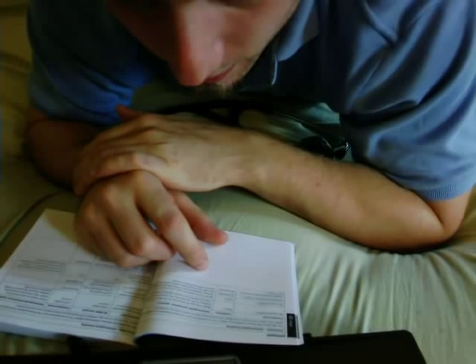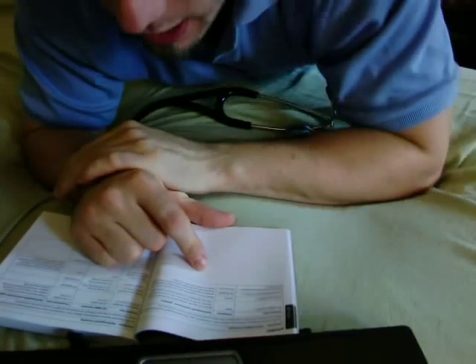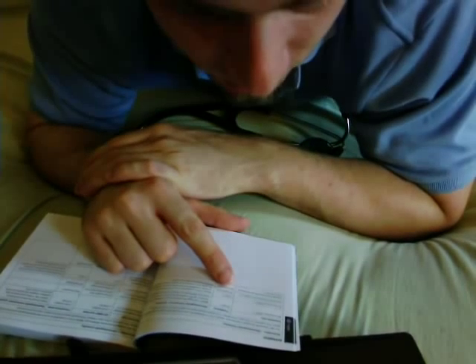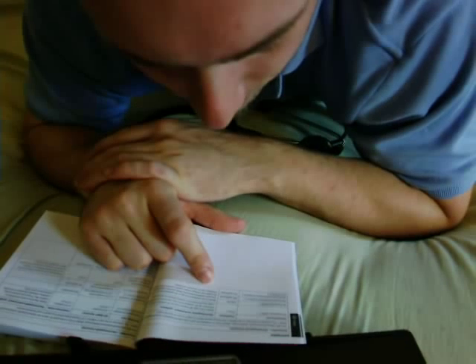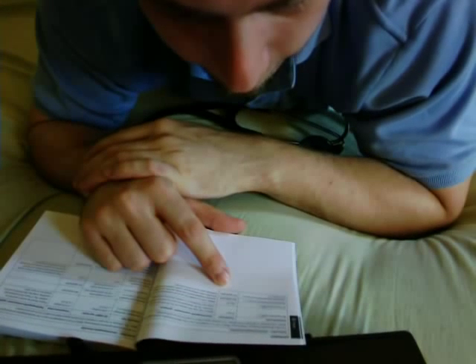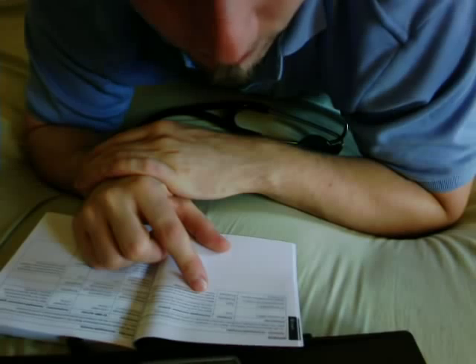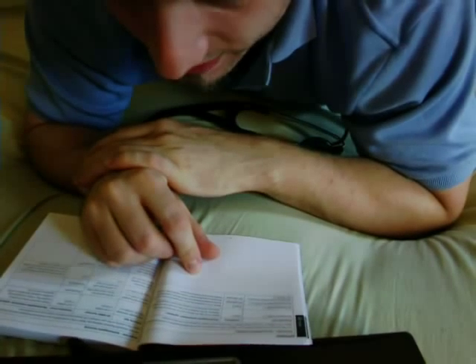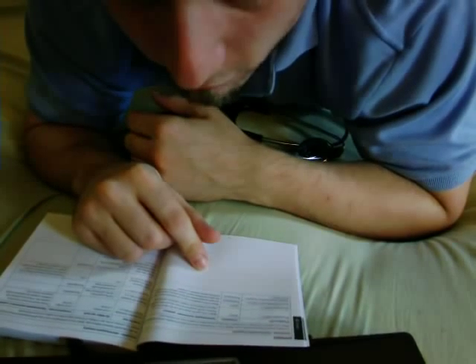The guidance states the model 3100 stethoscope uses RF energy only for its internal function, therefore its RF emissions are very low and not likely to cause interference in nearby electronic equipment. Next: RF emissions CISPR 11 Class B, harmonic emissions IEC 61000-3-2 — not applicable, voltage fluctuation/flicker emissions IEC 61000-3-3 — not applicable. The guidance notes the model 3100 is suitable for use in all establishments including domestic ones connected to the public low-voltage power supply network.